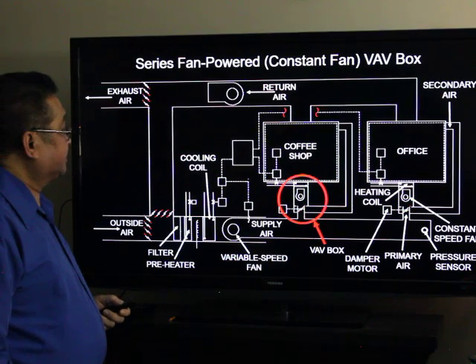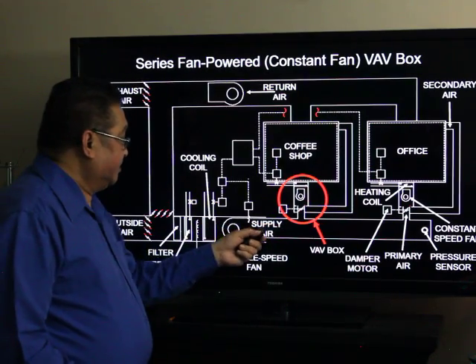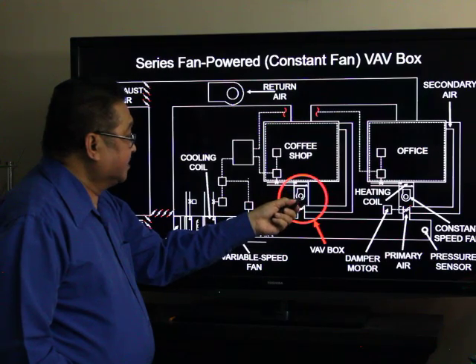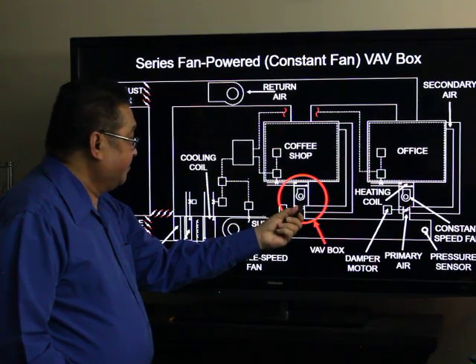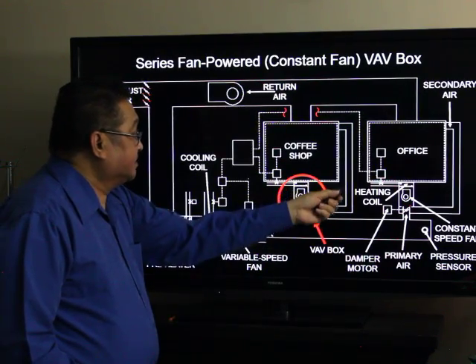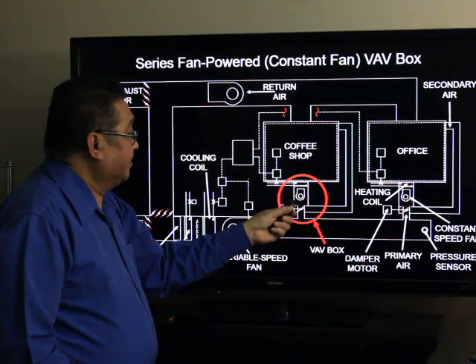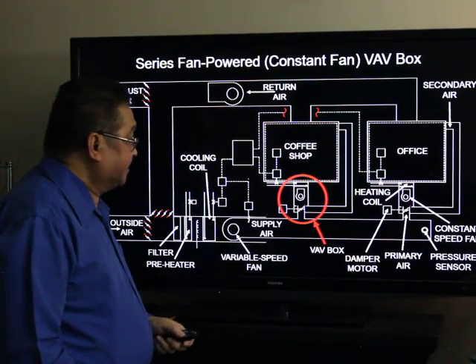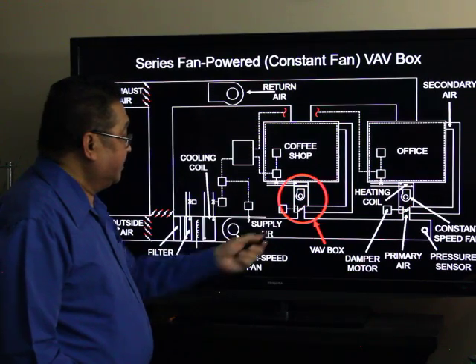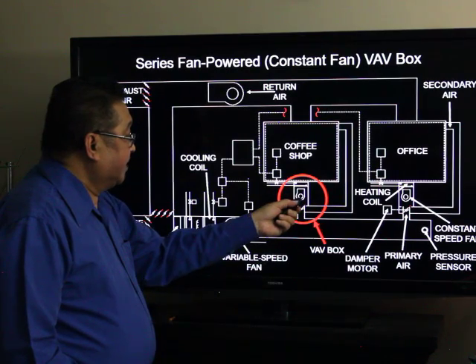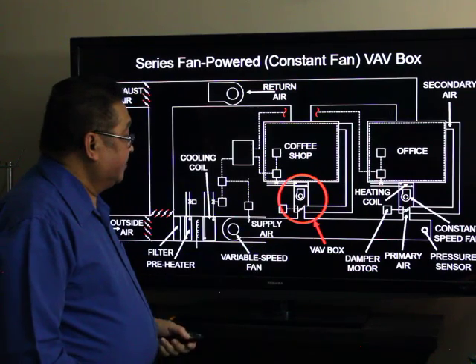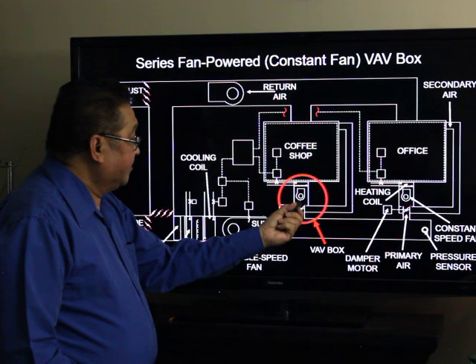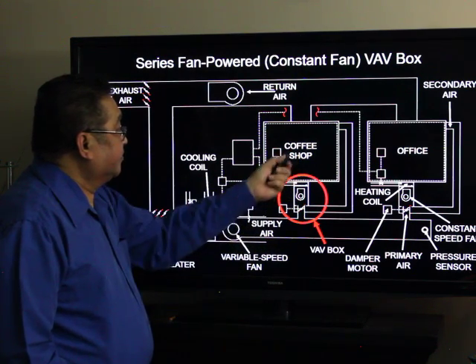In the series fan powered VAV box, the cold supply air is controlled by a damper in the VAV box, with a motor running at constant speed. As you close the supply air damper, more secondary air is drawn in and recirculated, maintaining a constant airflow going to the zone. Because the fan is of constant speed, the cooling requirements will be the one used to size the fan. During summertime when it's very hot, the damper will be fully open and you will need the proper CFM to supply in order to cool down the people in the coffee shop.